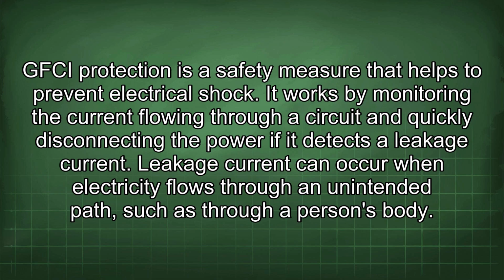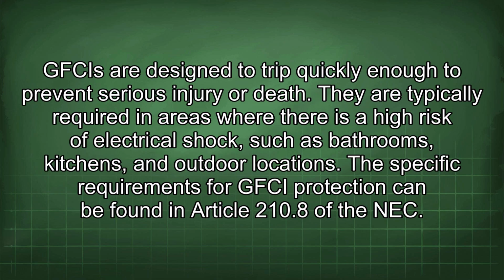It works by monitoring the current flowing through a circuit and quickly disconnecting the power if it detects a leakage current. Leakage current can occur when electricity flows through an unintended path, such as through a person's body. GFCIs are designed to trip quickly enough to prevent serious injury or death. They are typically required in areas where there is a high risk of electrical shock, such as bathrooms, kitchens, and outdoor locations. The specific requirements for GFCI protection can be found in Article 210.8 of the NEC.